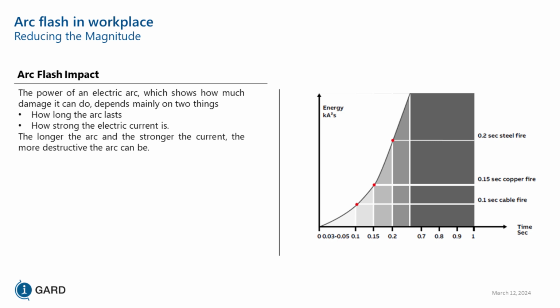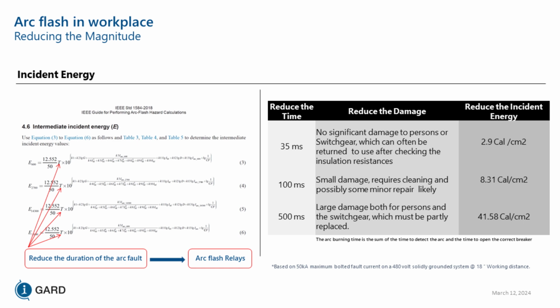You guys have seen these before, right? In 1 second, 0.1 second cable fire, 0.15 seconds copper fire, and 0.2 seconds steel fire. All we're trying to find out here is that incident energy is directly proportional to time. This is why you have to have zone selective interlocking, zone differential protection. We're trying to minimize the time that the fault is on the system and have faster reacting relays to trip when there's a fault in your system, because when there's a fault in your system, you're most likely will have an arc flash.